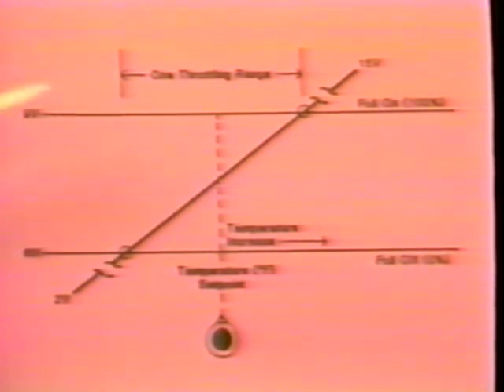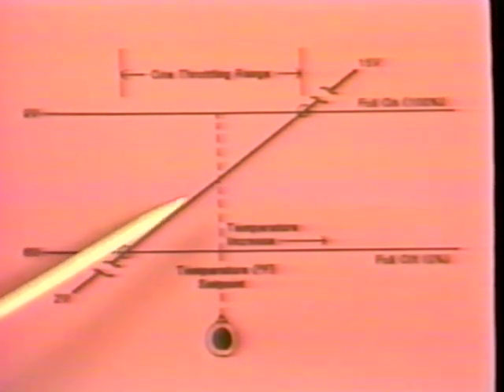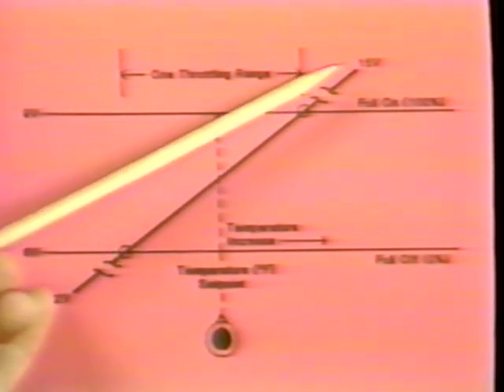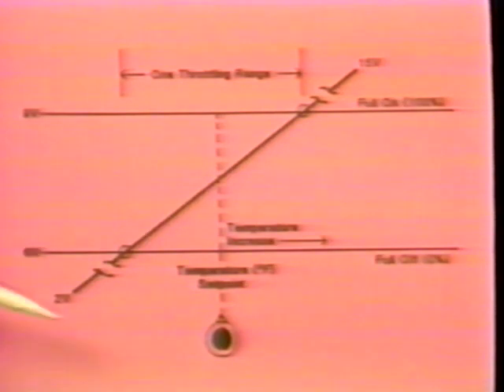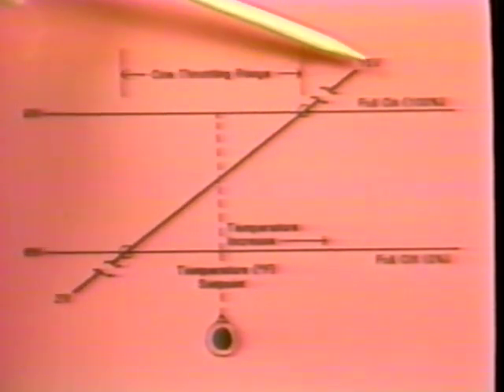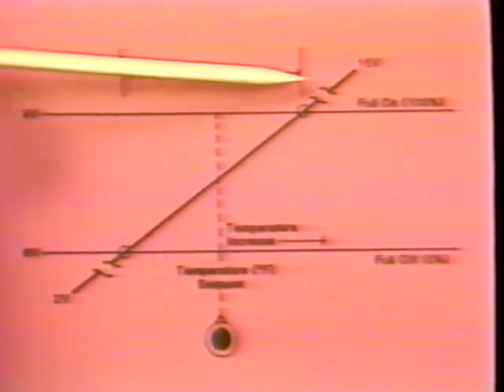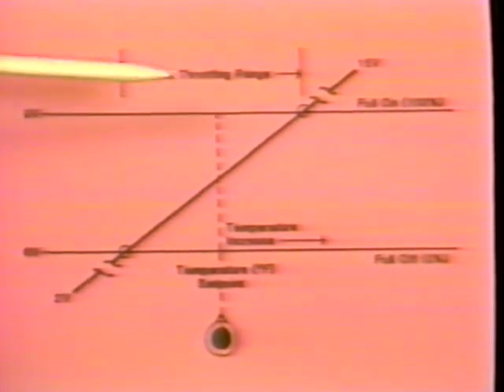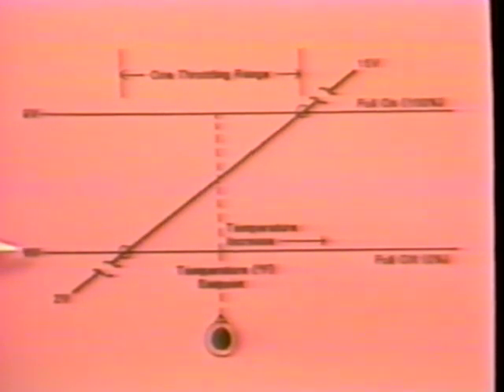This diagram illustrates direct action. Note that as the variable, in this case temperature, increases, the voltage signal from the controller also increases. One other thing to note, even though each controller has a wide output voltage, in this diagram from 2 to 15 volts, the throttling range adjustment on the controller is much more limited. It refers to a 3-volt change, as illustrated here, from 6 to 9 volts.